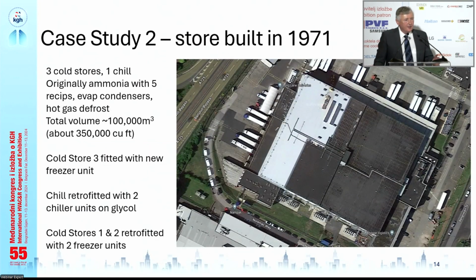Second case study is a cold store in Scotland. And this one was built in 1971, so the fabric is in very poor condition. And the original refrigeration system, an ammonia system with reciprocating compressors, was in fairly bad shape. The compressors were not efficient, they were not reliable, they had a lot of ammonia leaks, they had a lot of disruption to their operation.